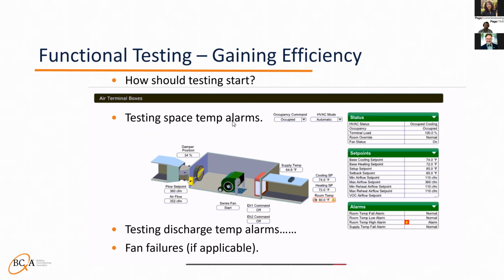If there are discharge temperature alarms on the terminal unit, suggest having the engineer or owner remove them. They're useless, unless it's a high limit cutout for an electric reheat coil, but that is different than a high discharge air temperature alarm anyways. For fan failures, if they're applicable, they're fairly simple. Usually you can override all the fan statuses at one time to be opposite of the command. If you don't feel comfortable with that, you can go to each one in the sample and remove the CT on the fan.